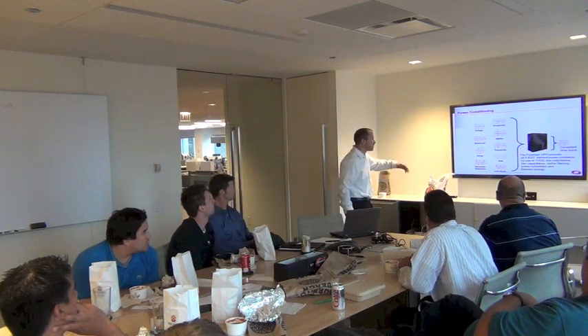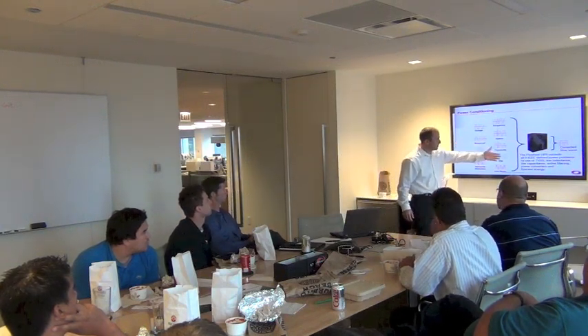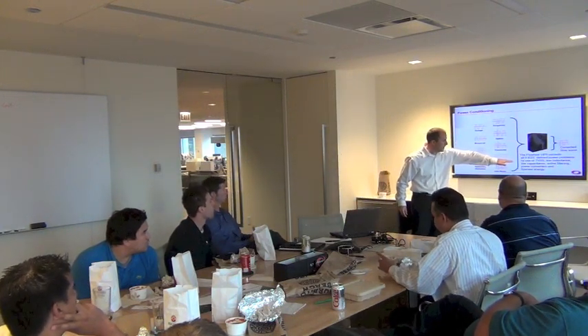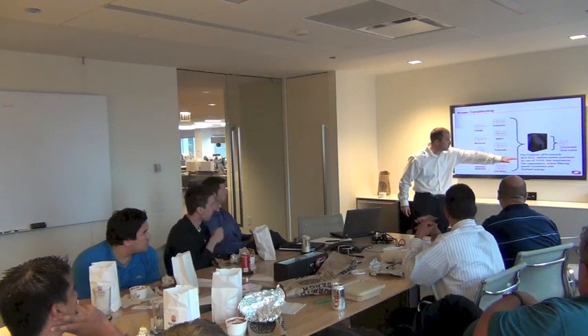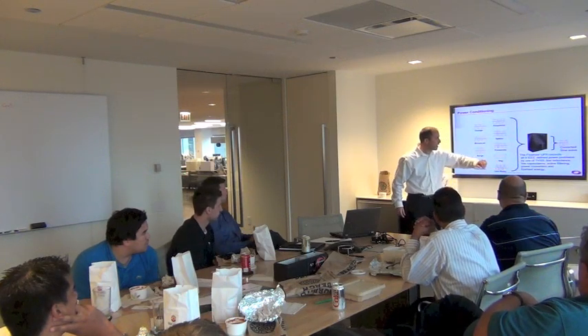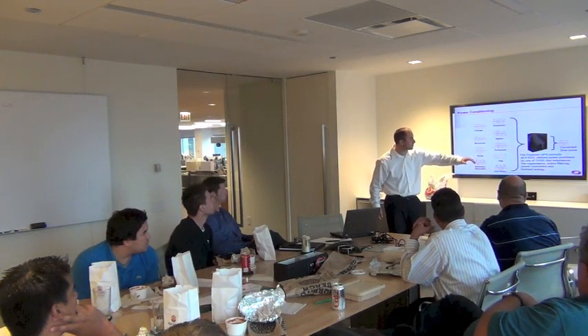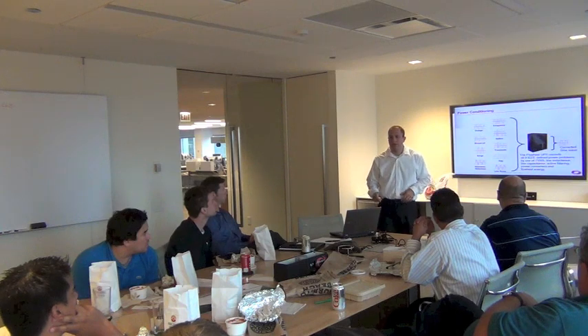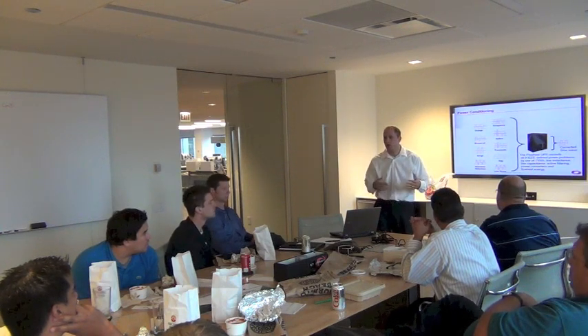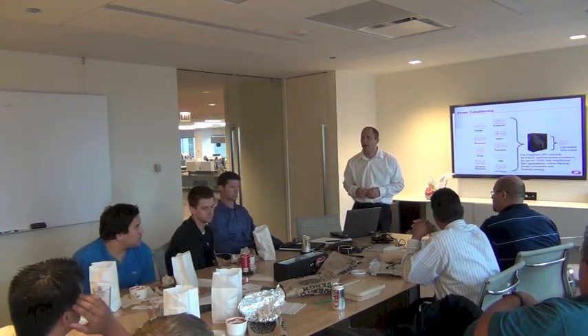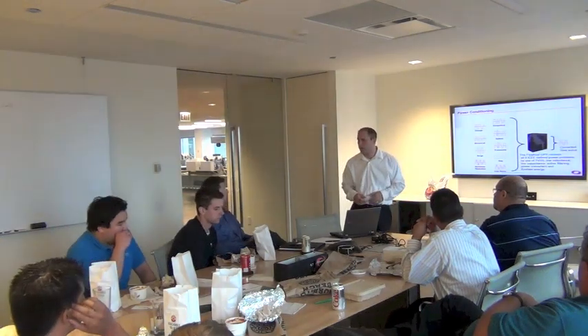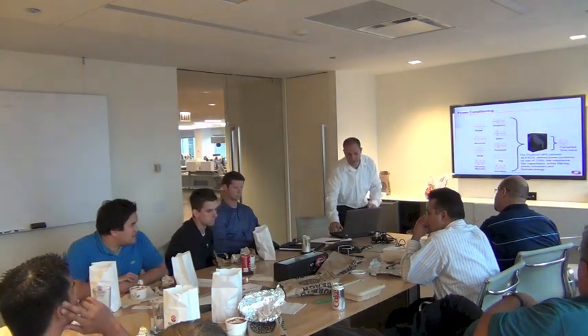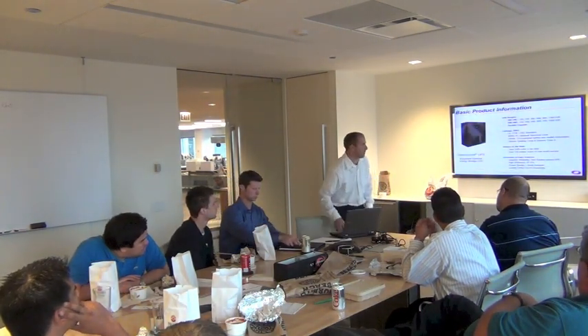Okay. So the Clean Source UPS corrects all non-IEEE defined power problems, and we talked a little bit about that: transient voltage surge suppression, line inductance, line capacitance, active control, power converters, and flywheel energy. Scott does have a handout here as well. It talks about how we correct each one of those power problems in a little more detail. If you're interested in that, there's a handout that goes through it.